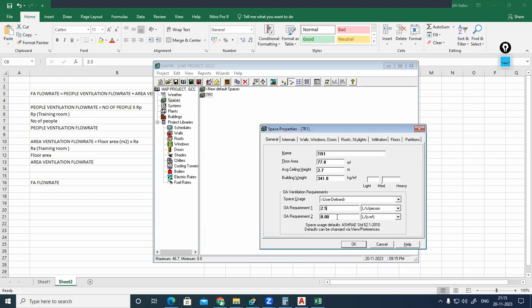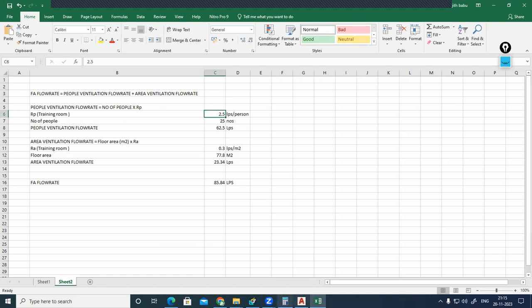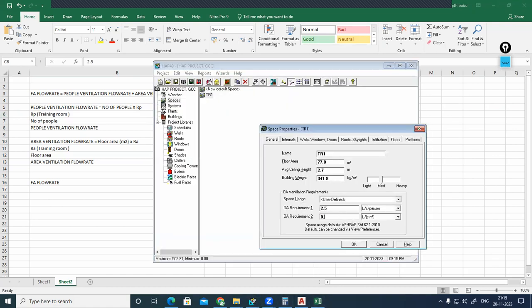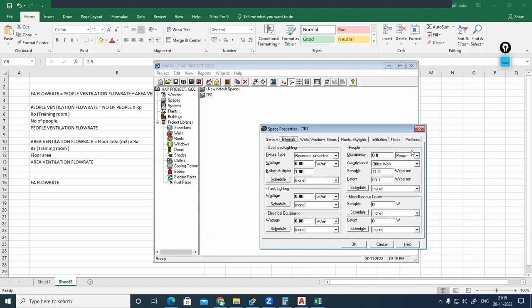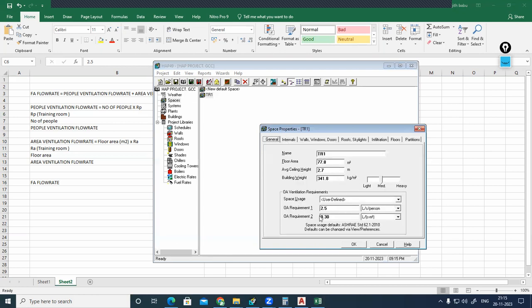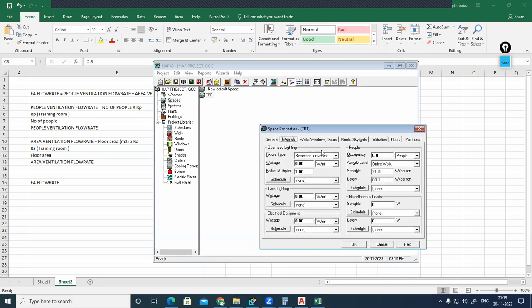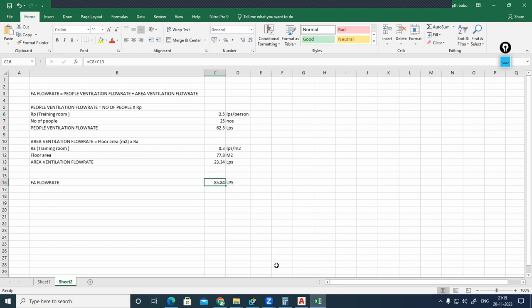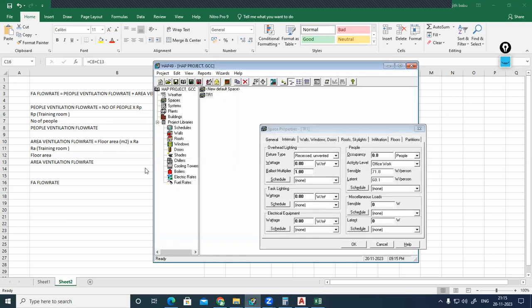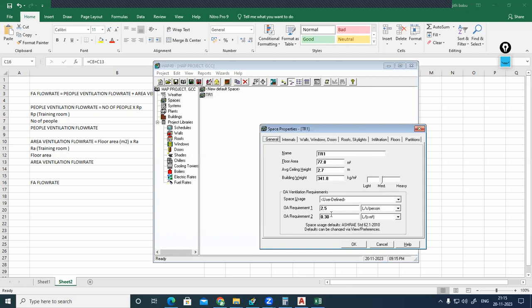Liter per second per meter square, that will be the Ra value, 0.3. We can give 0.3. Now what will the software do? The software will multiply this 0.3 with the 77.8, so it calculates the area ventilation. The software will multiply this 2.5 with the people. We have not provided the people input. Later we will provide it. At that time, the software will multiply this 2.5 with the number of people. Accordingly, the software will calculate the same flow rate. Correct? So that is somewhat easy, right? You don't want to do the manual calculation. Just provide the Rp and Ra values. But the easiest one, let me make this zero.